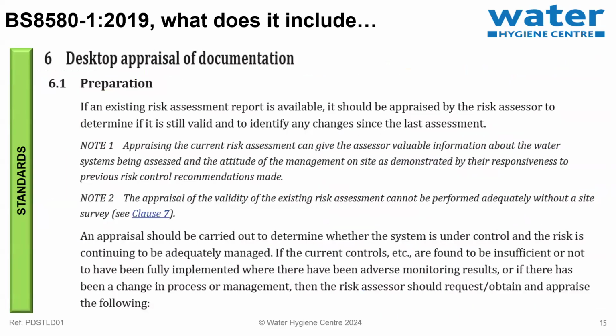Okay, so what do we do when we're on site? Do we do a desktop appraisal of documentation? This is really a review of the information that you've got readily available. When those enforcing organisations come on site, they will ask you for your risk assessment, they will ask you for a water risk policy, they will ask you for your written scheme or water safety plan, and they will ask you for the records.